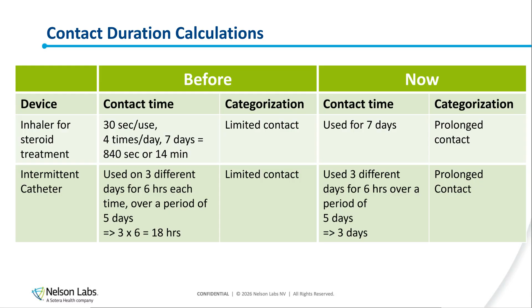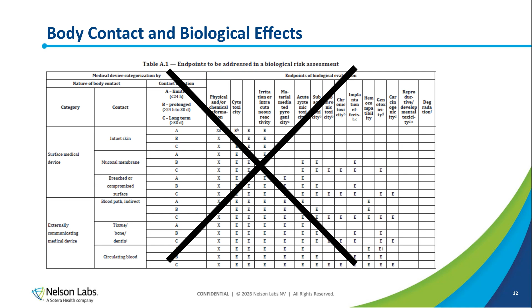Another change is the body contact type and the biological effects for consideration. So this is table A1 that was in ISO 10993-1 2018. This table was used to look at the nature of body contact, contact duration, and then get an understanding of what biological endpoints were to be considered for your device. The same principle is applicable for the 2025 version, but the presentation is slightly different. It's actually not one table anymore, it's four tables.